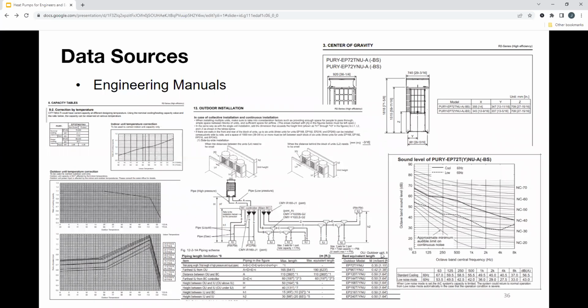If you're looking for more information, you can't really find it on the submittal. All manufacturers have uploaded engineering manuals under the certain equipment. And these are some of the things that we like to offer and that you can find in here. One being corrected capacity tables. This is actually built into all the equipment software. But if you are looking for certain power inputs and power ratios based on drop in space temp or drop in ambient temperature, that would be the place to look, right? There's outdoor installation, what are the clearances? You have your piping parameters, what you need to follow, weights, center of gravity, and then also sound levels. So there's a lot of information in engineering manuals that you might not know or might not have in your submittals, your cut sheets.